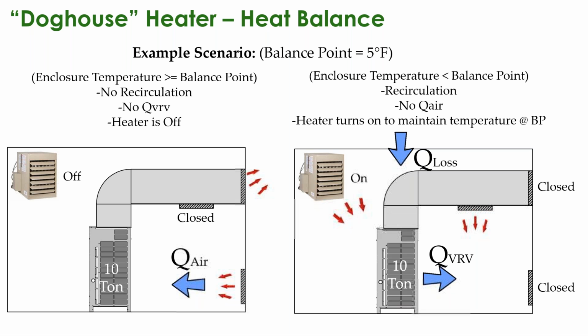Once the temperature drops below the balance point, we go into a recirculation mode where we close the discharge air off of the condenser, we close the inlet air onto the enclosure, and we recirculate that air from the condenser. At that point, you have the loss of the space, as well as the variable refrigerant system pulling heat out of that space. And that's when the heater will turn on to maintain the temperature that was calculated in your balance point.